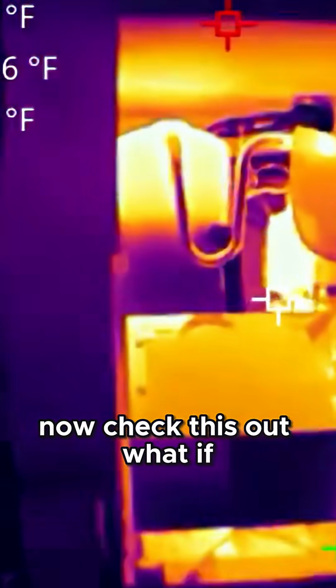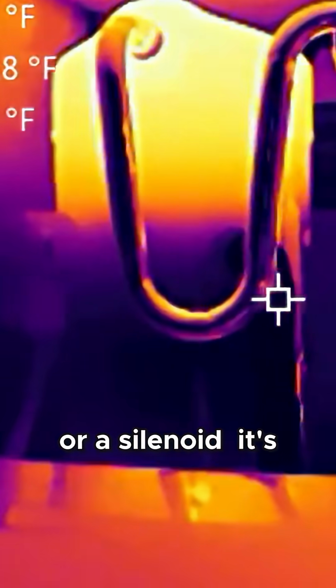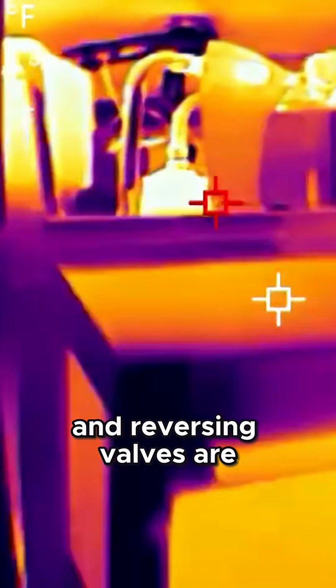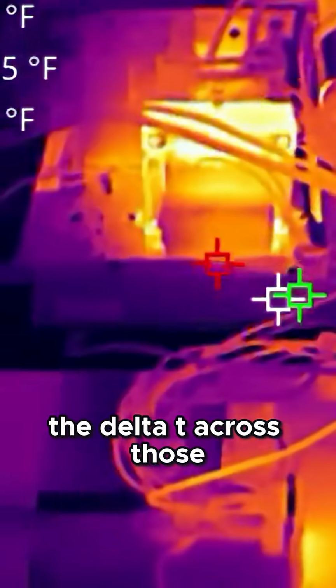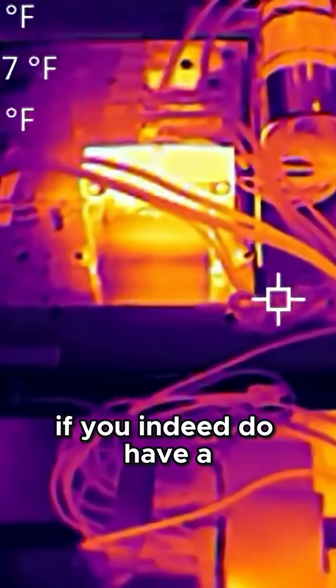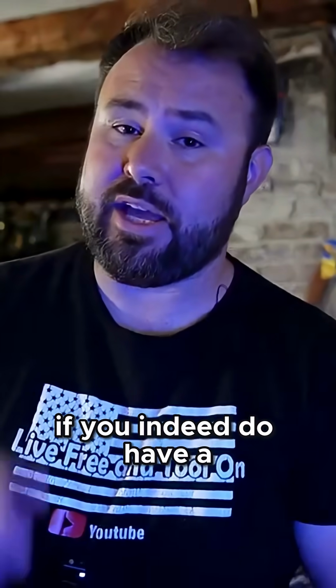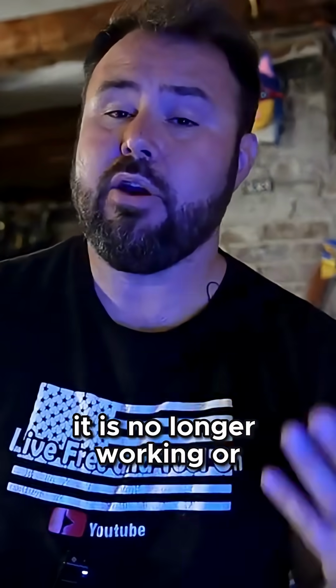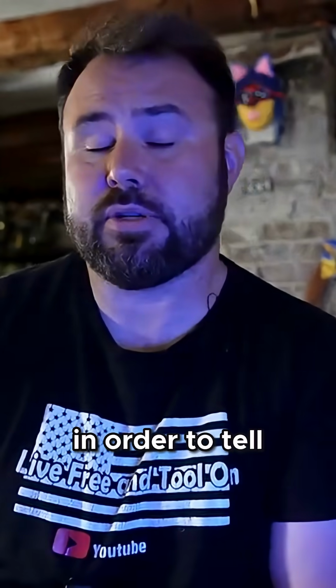Now check this out. What if you have a reversing valve or a solenoid? It's really good to know the temperature of those solenoids and reversing valves and the delta T across them, because that could indicate if you have a solenoid that has stopped working, so the slide valve inside of it is no longer working. Or if you have a reversing valve which is failing as well, you can do a lot of different things to tell what that is.